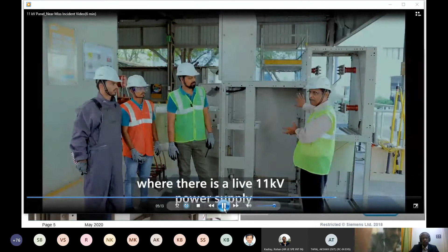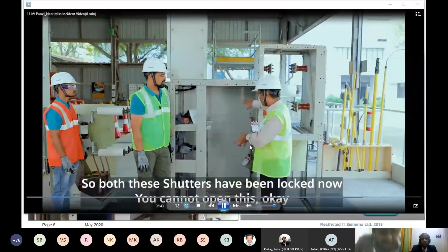What could have been done to prevent this? You have to put a LOTO on the shutter. Please do it, Manish, apply the LOTO. Now he is applying the LOTO for the shutter - this one is for the incomer side, and now he is applying one for the outgoing side. So both these shutters have been locked now. You cannot open this, okay?